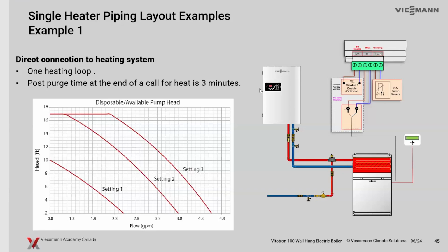And now, based on outdoor air temperature, we've got the sensor connected. We have a heating curve. It would fire based on whatever the temperature was that day and the heating curve that you have selected. So we see direct connections, return on the right-hand side, supply out. And of course, we've got the air vent inside of the boiler. We've got another little air scoop connected here, but some pretty simple wiring.